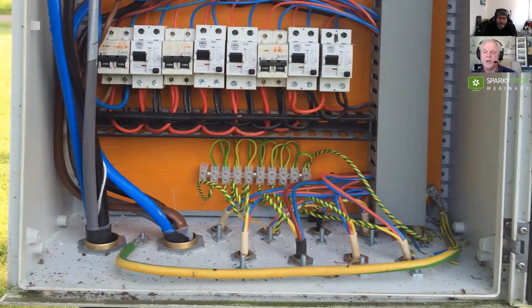So under short circuit conditions, what's going to operate? Well, you're going to have a current relative to the impedance of your path, which is going to be fairly low because it's going to be quite a high impedance in that pathway. And the overcurrent required would be substantial if the overcurrent device is actually back at the origin. You're probably talking, well, more than minutes, maybe hours. So this lot's probably going to catch fire then. Yeah, most likely.